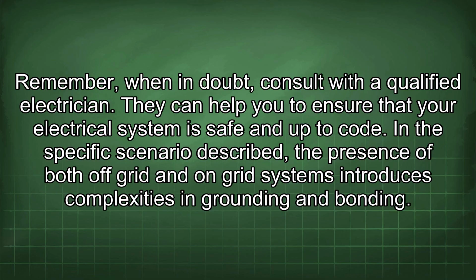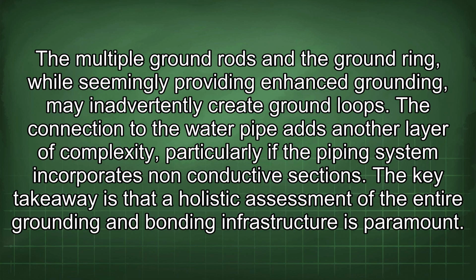In the specific scenario described, the presence of both off-grid and on-grid systems introduces complexities in grounding and bonding. The multiple ground rods and the ground ring, while seemingly providing enhanced grounding, may inadvertently create ground loops. The connection to the water pipe adds another layer of complexity, particularly if the piping system incorporates non-conductive sections. The key takeaway is that a holistic assessment of the entire grounding and bonding infrastructure is paramount.